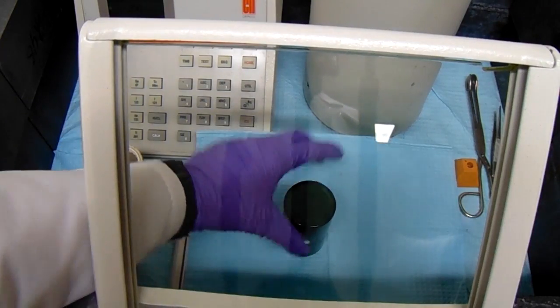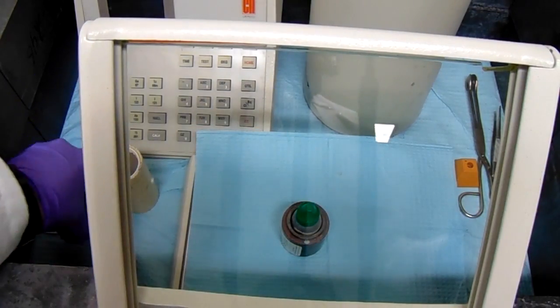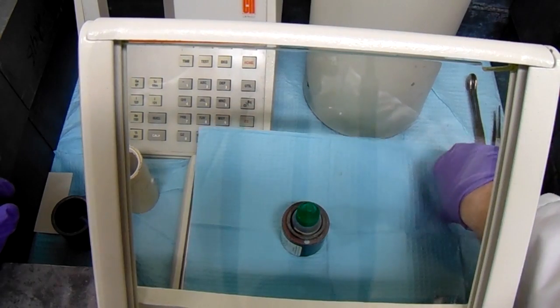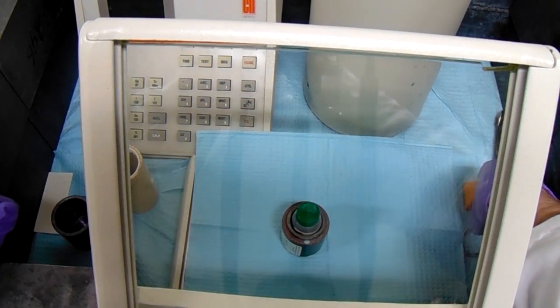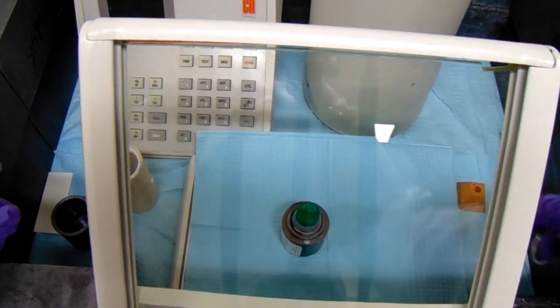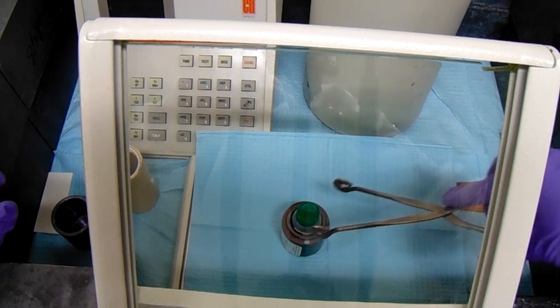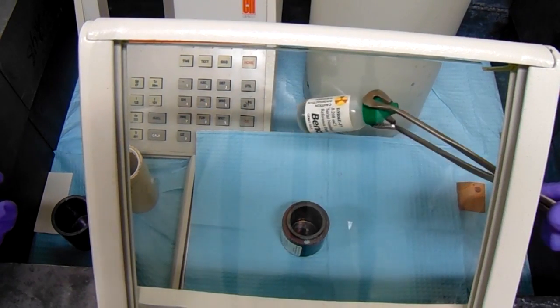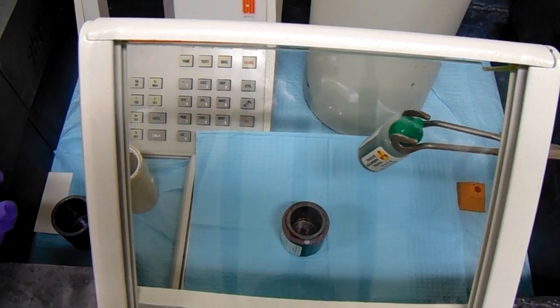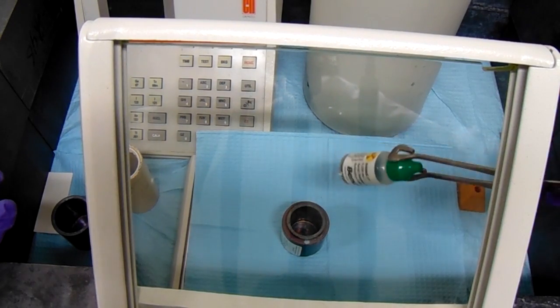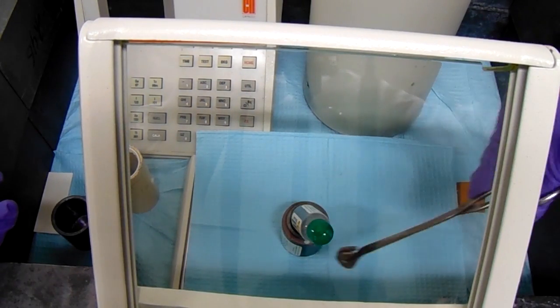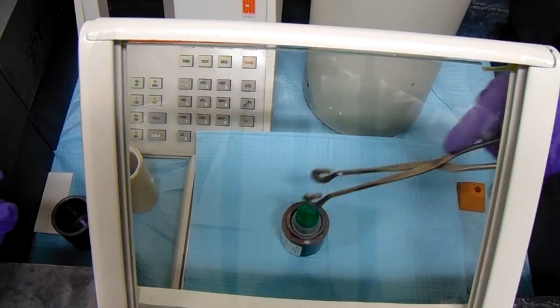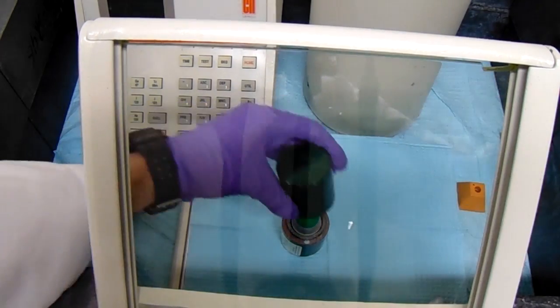Now we're going to do our constancy on our calibrators, and for that we use this liquid cesium source. It's in a separate little plastic vial as opposed to the bar, so you have to be careful when handling it because it might unscrew or spill or do something else, so always use your tongs when handling this source.